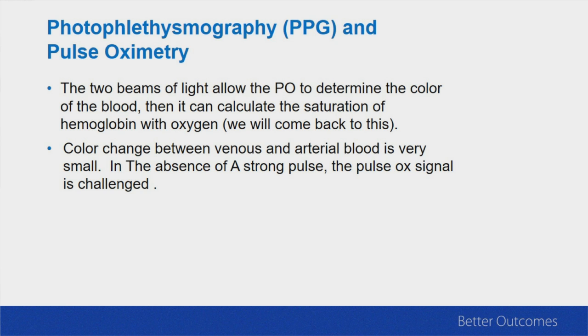Those two beams of light go through, some gets diffused, some gets absorbed by oxygenated or deoxygenated hemoglobin. And what that pulse ox is actually doing, it's determining the color of the blood. It's determining the color of the arterial blood, and it's determining the color of the venous blood. And then it gives you a saturation of the hemoglobin with oxygen. Well, that's a story we're going to come back to later. Now, the color change between venous and arterial blood is very small. So in the absence of a strong pulse, your pulse ox signal is going to be challenged and it's going to come into question.